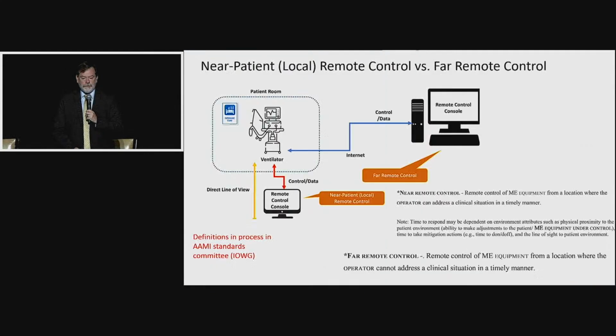Notice on line 237, on the bottom right, it says conformance testing for electromagnetic compatibility is recommended but not required. Why would it not be required? Because this was an emergency use process - there wasn't enough time to do all these things, and there wasn't the capacity in the testing world to test all of them. So we really took a risk-based approach: what were the likely hazards, and what could you test in the time allotted, in order to get this out the door.